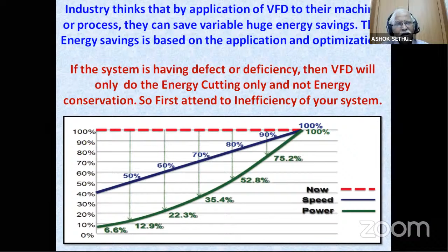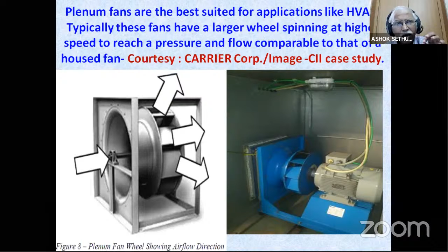The energy efficient recent trends in the fans are, people are not going for the centrifugal type, backward curved, forward curved, all these things. From forward curved, they went for backward curved, backward flat, and then backward curved. Now they are going for plug fans or plenum fans, which are high volume, high diameter, and the volumes are more and the static pressure is less, but it is able to achieve the same system efficiency. It has been deployed in all the AC equipments now. You can check for yourselves.